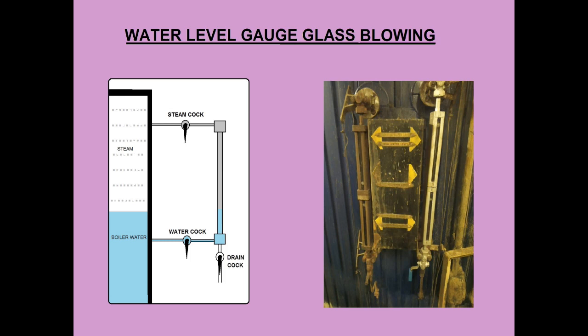Blowing procedure of water level gauge glass. The figure shows a gauge glass directly attached to the boiler shell. First close the steam and water cocks, then open the drain. If the steam and water cocks are holding, nothing should blow out from the drain cock. Now open and close the water cock to check the water line is clear from any obstruction. In the same way, open and close the steam cock to check the steam path is clear. Once confirmed both steam and water paths are clear, close the drain.